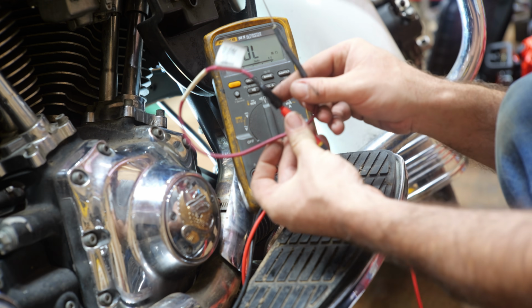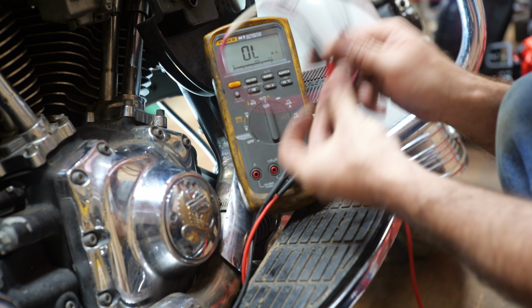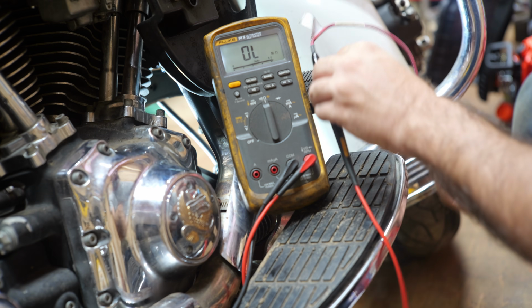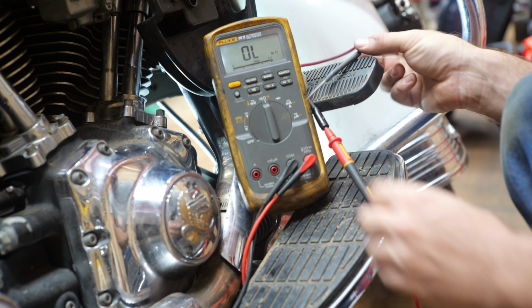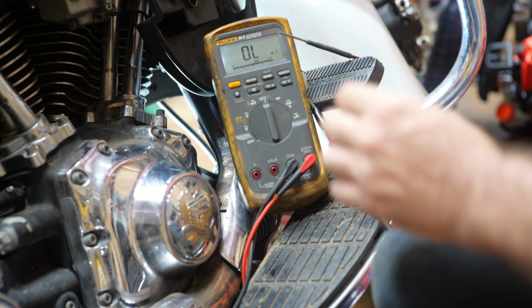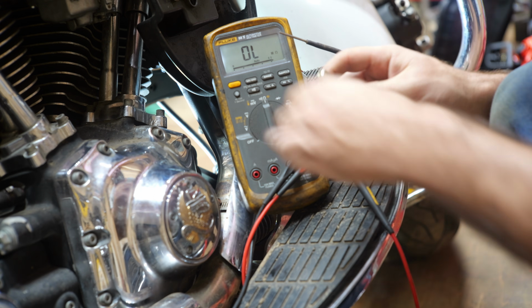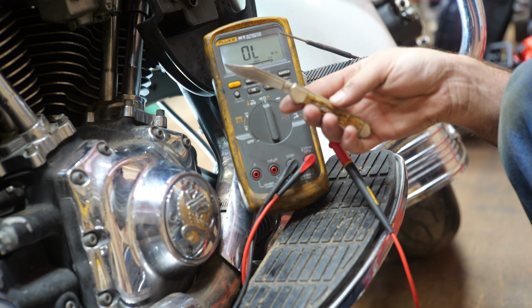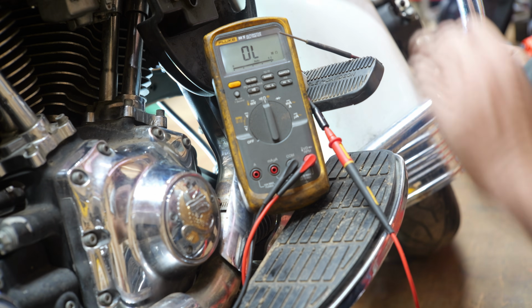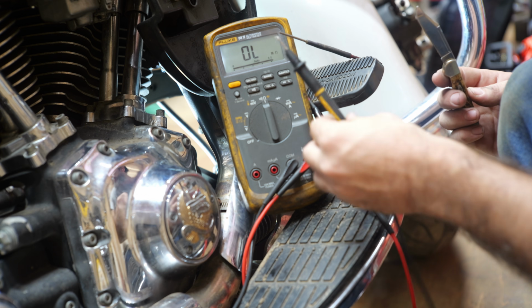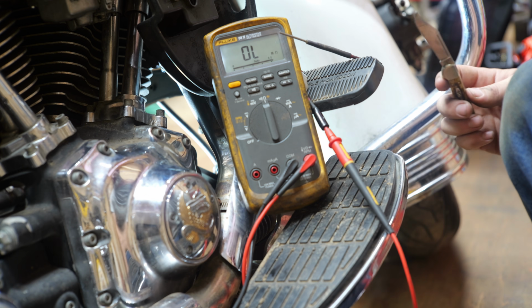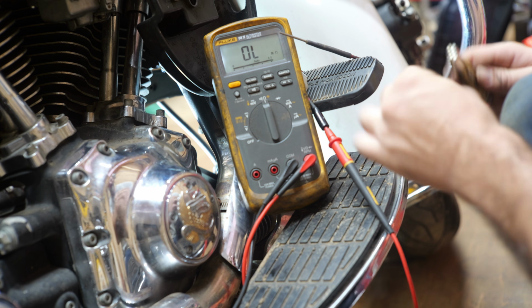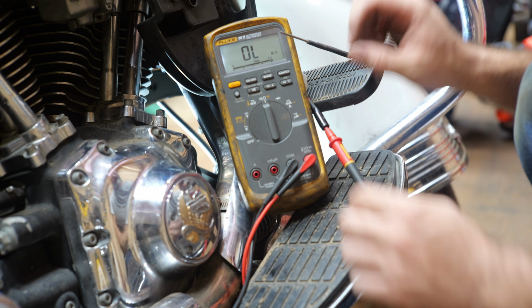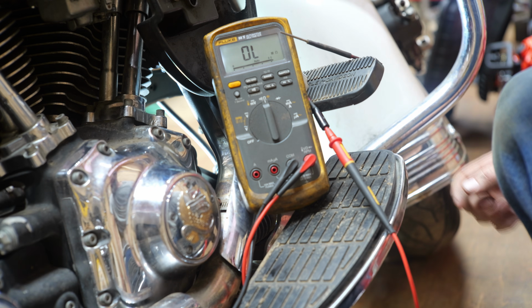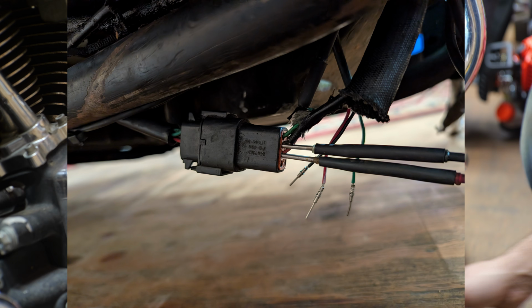This is the correct way to back probe a connector, especially Deutsch connectors, but really any connector. What you don't want to do is what I see so many guys do: take out their old pocket knife, skin back the insulation of the wire, and shove the lead of the multimeter into that bare copper. Don't do that, not acceptable. You also don't want to go poking little holes in the wires with needle alligator clips. Don't do that either. Use an actual back probe spoon.